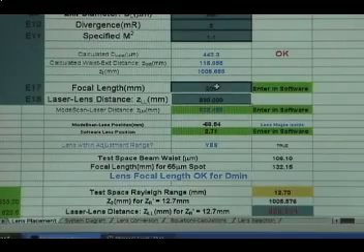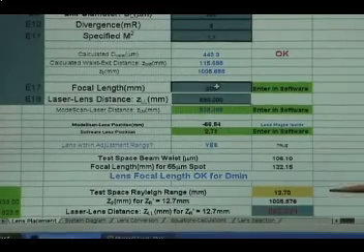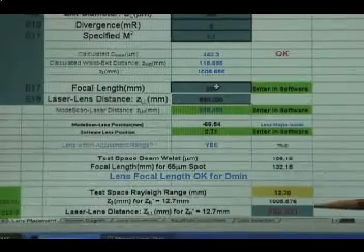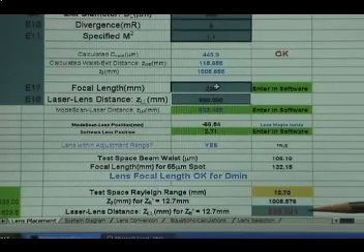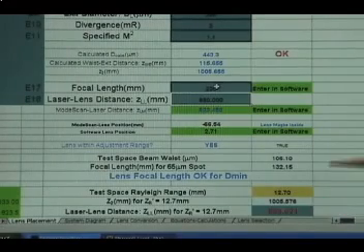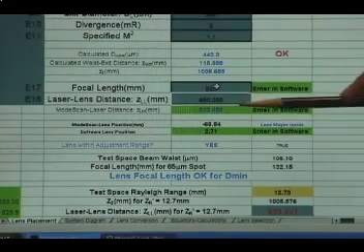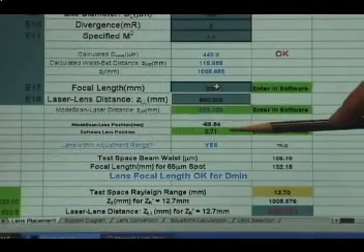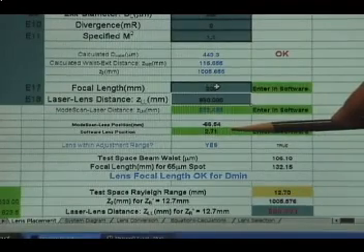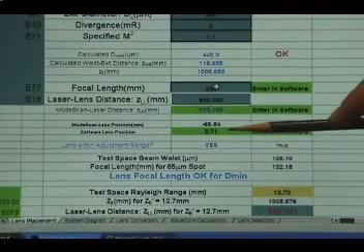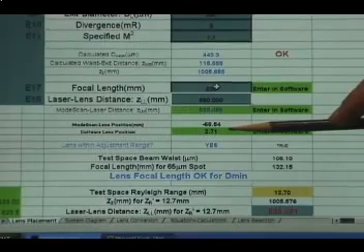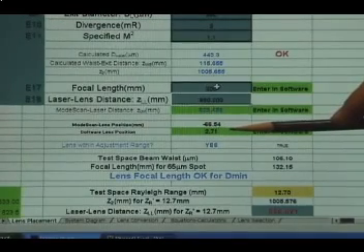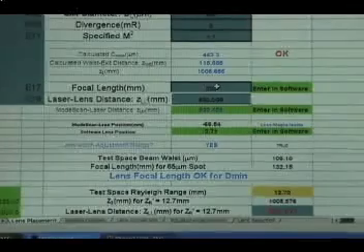The calculator calculates an optimal laser lens distance of 890 millimeters which corresponds to a mode scan laser distance of about 820 millimeters. There's another parameter the calculator calculates called the software lens position which here is 2.7 millimeters. I'll explain what that means later but we have all the parameters now to set up the test.